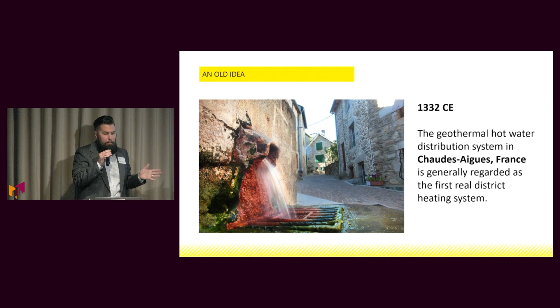But we can tap into geothermal without hot water because of heat pumps. We couldn't do this 100 years ago, but now, just like we use that lukewarm water in the streets of a city as a shared platform, if I pipe that water deep underground, the temperature is stable in bedrock—it's the same all year long. So I can pull endless amounts of energy out and dump endless amounts of energy in, because that bedrock will absorb or put out way more heat than I'll ever be able to tap into. And because we have warm water in the streets from our community energy system, I can pipe that energy into that shared platform.